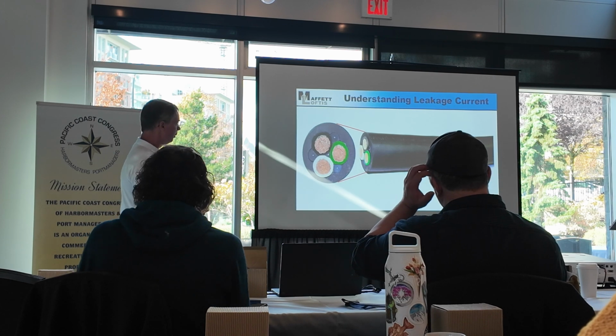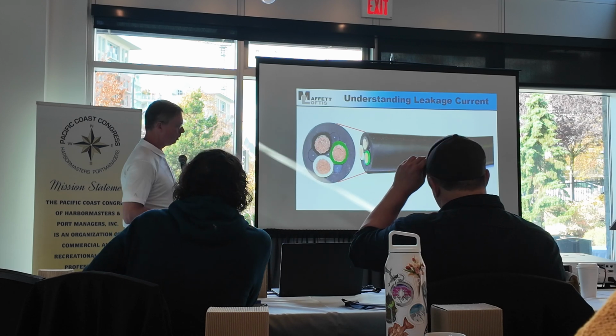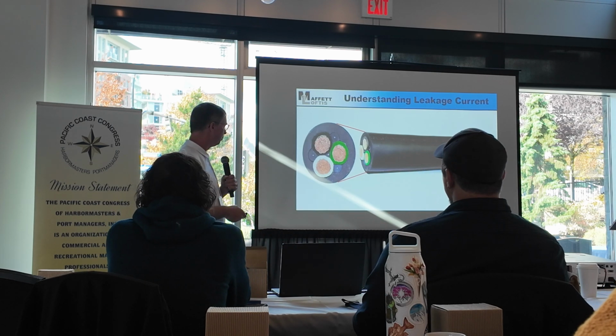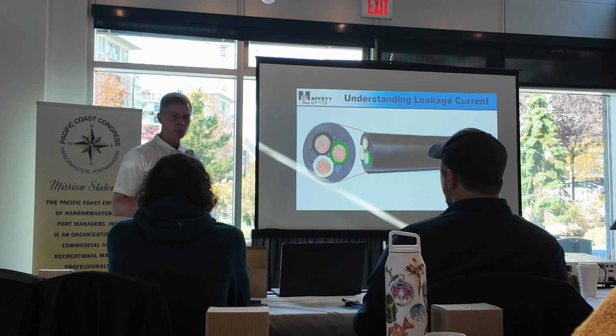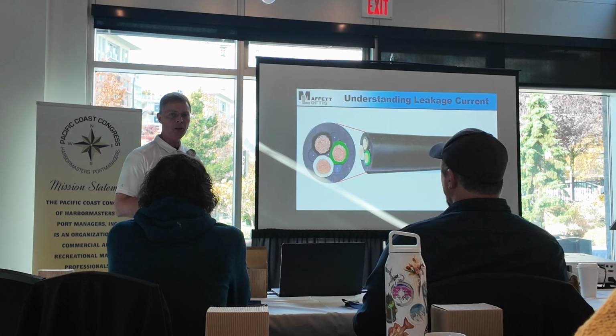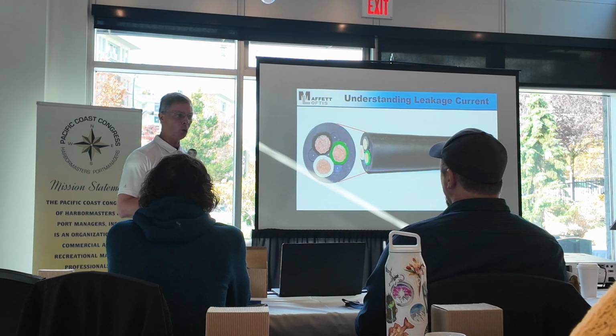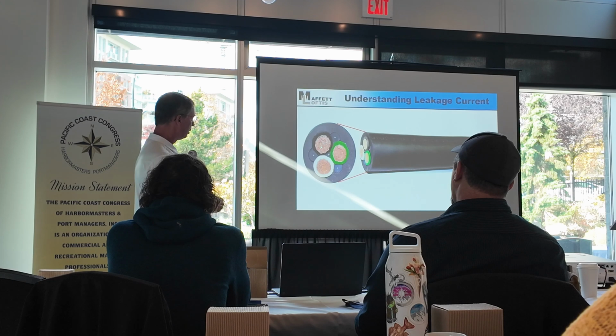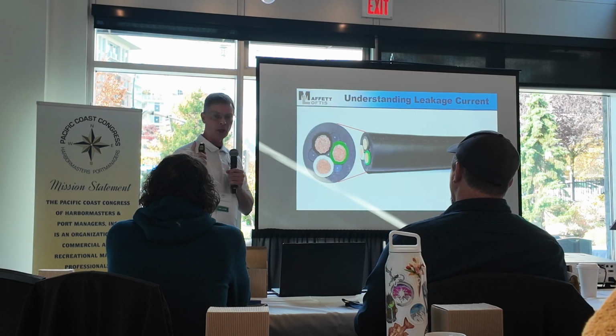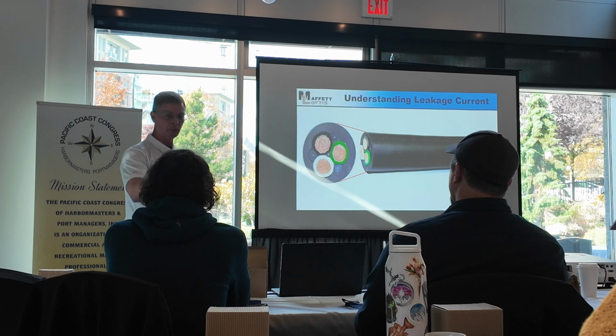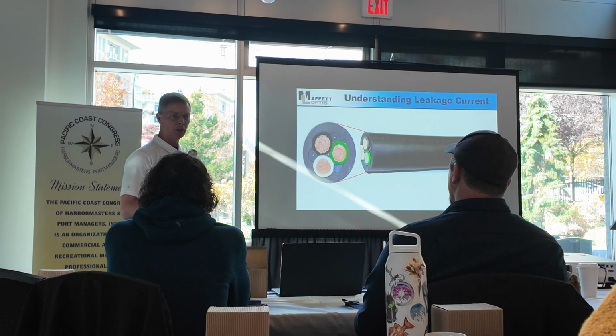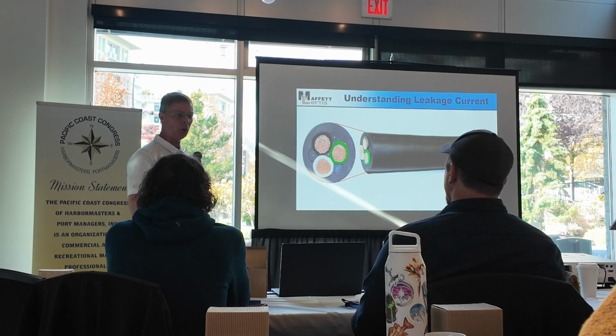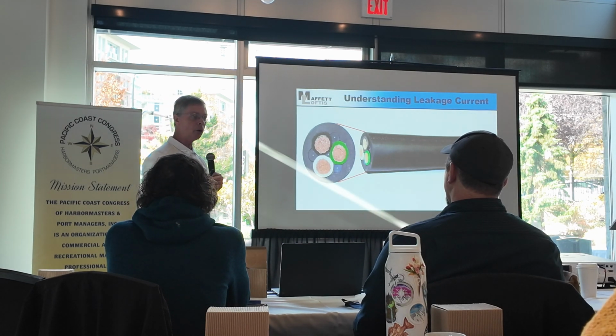And if you look at this, this is really type W cable, but imagine that's a shore power cord. This will be a 30 amp, 120 volt cord, because it's only 3 conductors. You got the black, the white, and the green. What does the black wire do for you? Hot. It serves power to the boat, right? What does the white wire do for you? Neutral. It returns power from the boat back to the source. What does the green wire do? It's the ground, the safety ground.